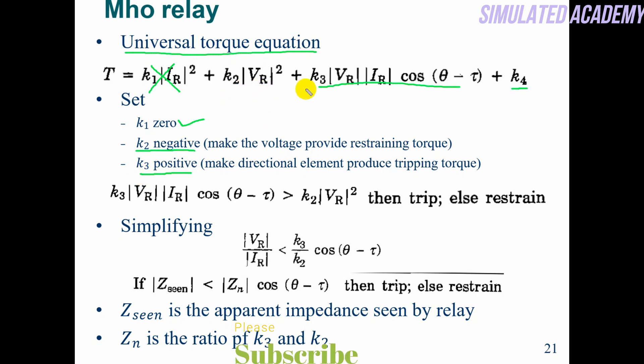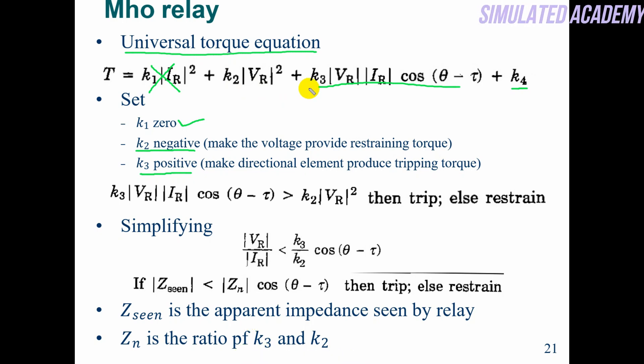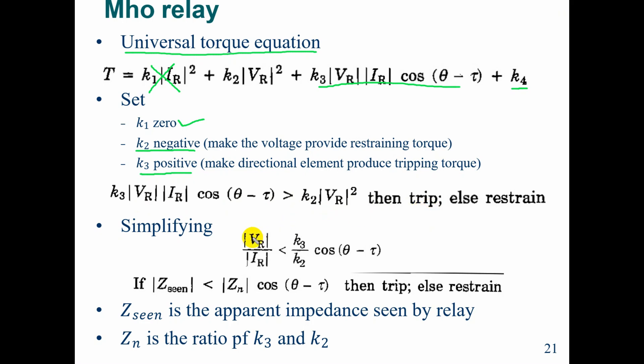So k2 will be the restraining torque while k3 will be the operating torque. k3 will cause the relay to operate. If the pickup flux is exceeded, the relay will operate. So if k3 × Vr × Ir × cos(θ − τ), where θ is the angle between voltage and current and τ is the minimum torque angle, is greater than k2 × V², it will trip; otherwise it will restrain. Simplifying, Vr/Ir < (k3/k2) × cos(θ − τ). If this condition is met, the relay will trip.